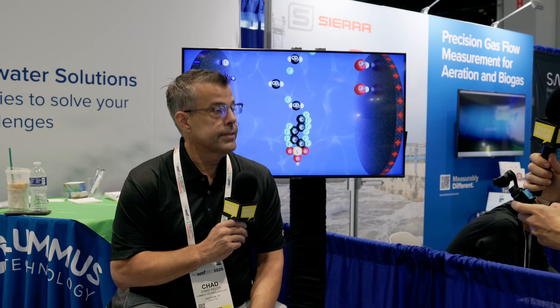We go two orders of magnitude higher current density than anybody else in the marketplace. Two orders of magnitude? Yes. If you look at conventional electro-oxidation using metal electrodes, they'll be in the hundreds of amps per meter squared. We can go up to close to 40,000 amps per meter squared. The fact that we can go to that much higher current density makes our system much more compact. When people hear about boron-doped diamond, they see dollar signs — but we have such high current density that we use two orders of magnitude fewer electrodes.